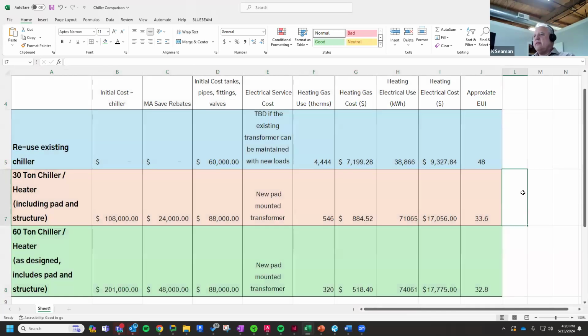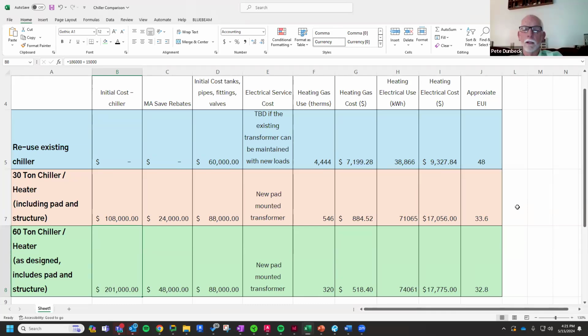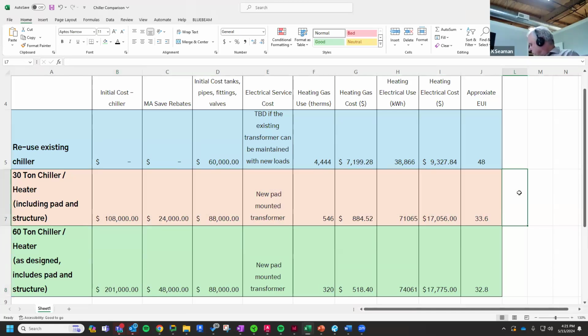Well, if we keep the boiler in play and they're not going to give us a rebate because of it, then an extra $75,000 for that additional chiller seems like it's going to be a payback that just won't occur within the life cycle of the chiller. I think it's prudent to go with the 30 based on these numbers. I'd like a little time to play with the numbers and confirm, but certainly this is pretty compelling that 30 is the better option.